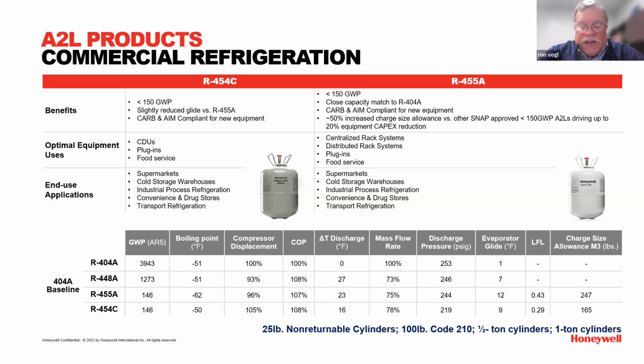If you've got two pieces of equipment, one's A1 and one's A2L, and it's the A1 that's leaking and the leak detector is general, it could just start shutting everything down, even though you have no problem with the A2L. So I don't want to give the impression that it's horrible, but that type of thing is still being worked through. But if it is specific to A2Ls, what I'm being told on the equipment mounted leak detection, is that it is specific to that A2L. So if you're going to use 454B, it'll be specific to that. And if you're going to use 32, it'll be specific to 32. Now, I don't know how they're getting that accurate, but that's what we're hearing.